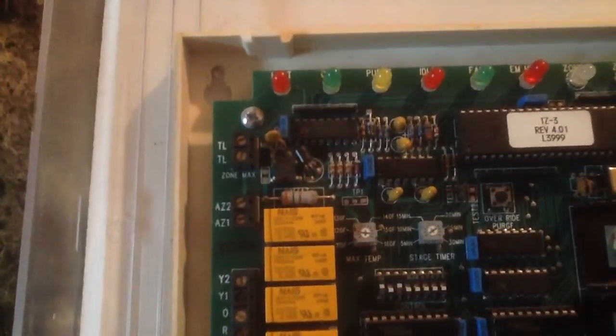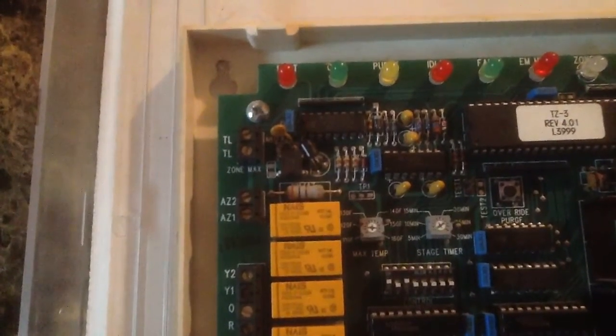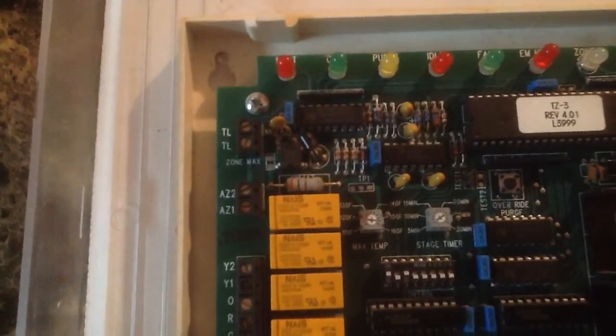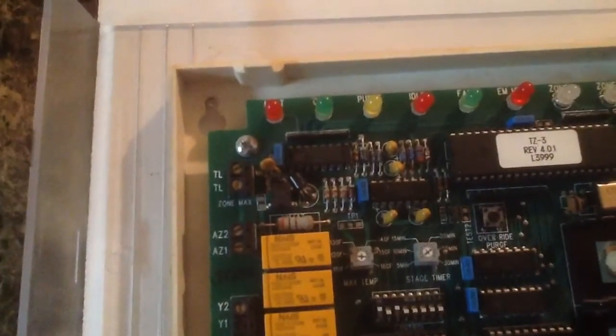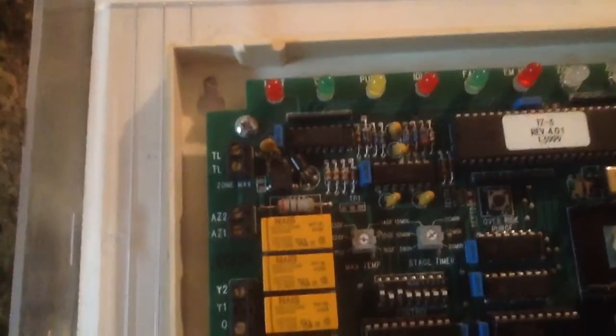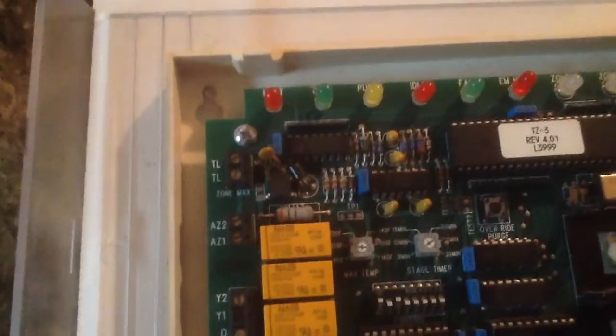So typically you want to definitely set it well below the main limit set point to make sure that if you only have one zone calling, if it gets too hot in the plenum, it'll actually turn the system off and go through a purge cycle, and basically just run the blower, cool the heat exchanger down, and then go through its time delays and fire it back up.